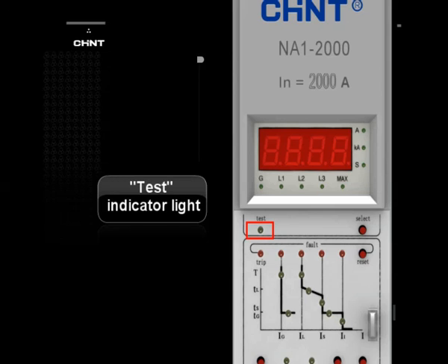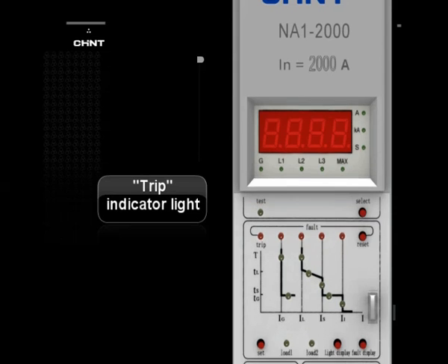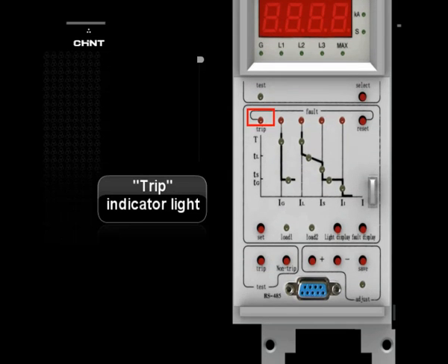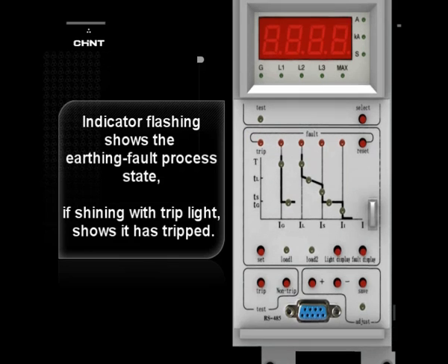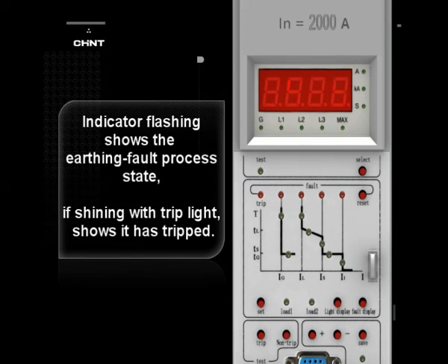Test Indicator Light: Indicates the breaker is in the test state. Trip Indicator Light: Indicates the release is sending out a tripping signal. Indicator Light: Flashing shows the earthing fault processing state. If shining together with the trip light, it shows that it has been tripped.